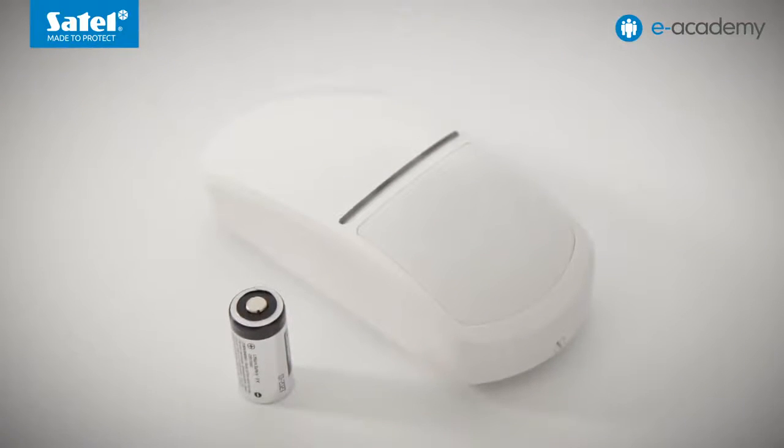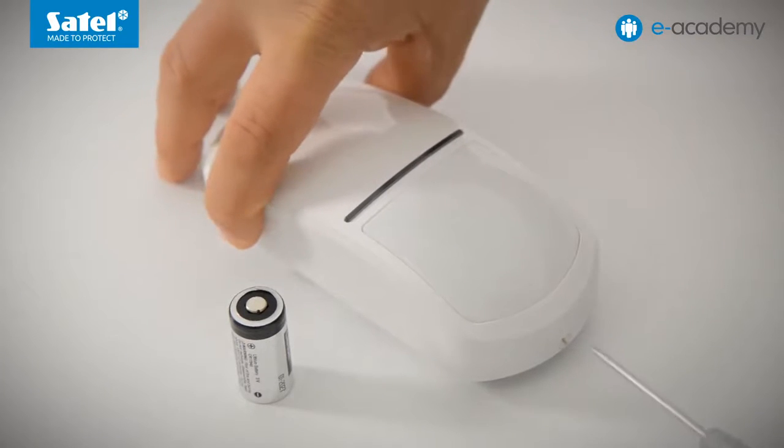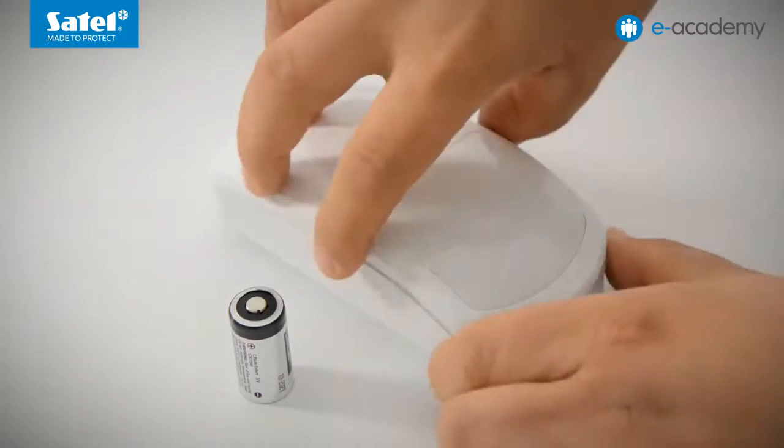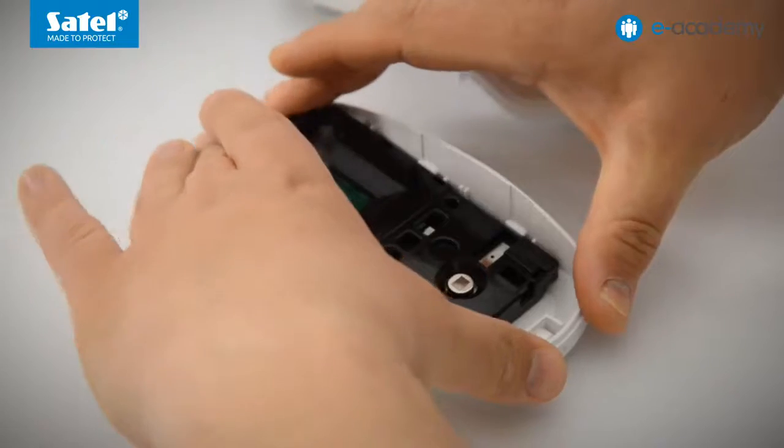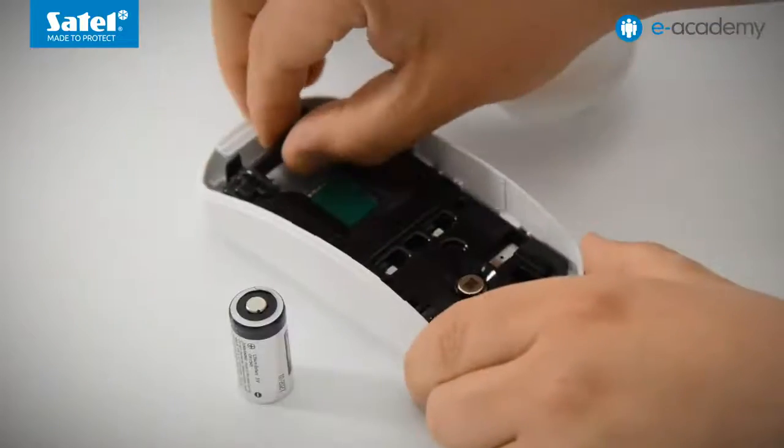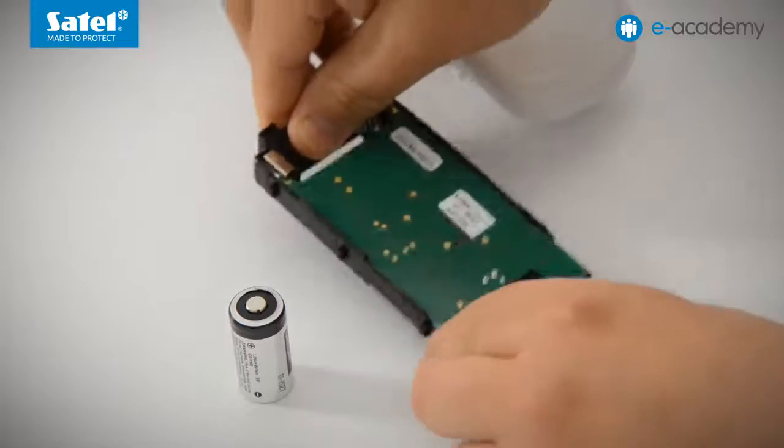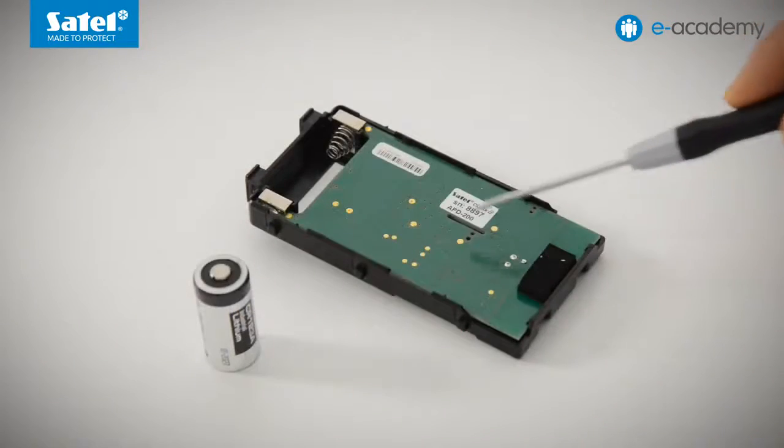As the first one, we will register the APD200 motion detector. To do this, open the detector enclosure by gently turning the lock. Remove the front part of the enclosure. Push down the electronics module to disconnect it, then carefully remove it from the enclosure. At the back of the module, there is a sticker with the detector serial number.